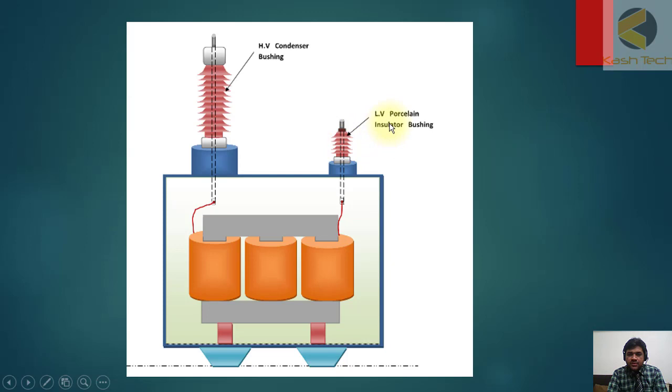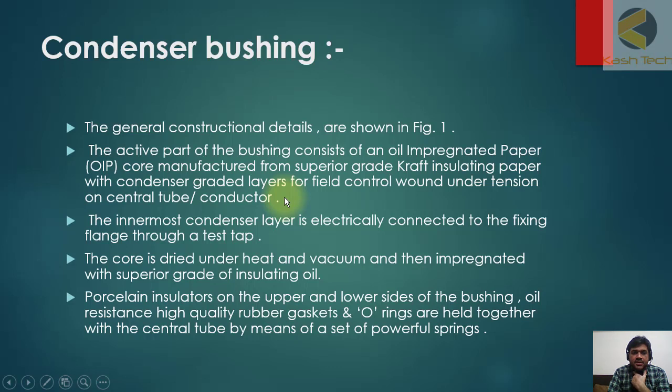The low voltage is of porcelain; the high voltage is condenser bushing. We will discuss condenser bushing. General constructional details are shown in figure one. The active part of bushing consists of an oil-impregnated paper core manufactured from superior grade kraft insulating paper with condenser graded layers for field control.